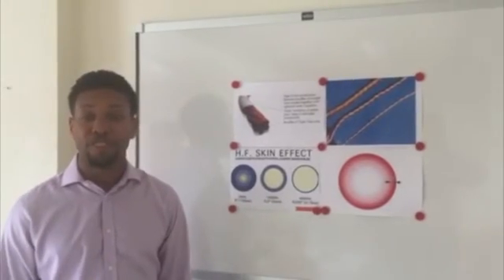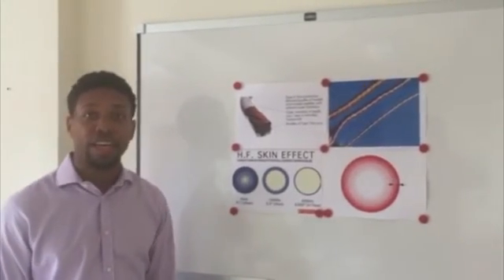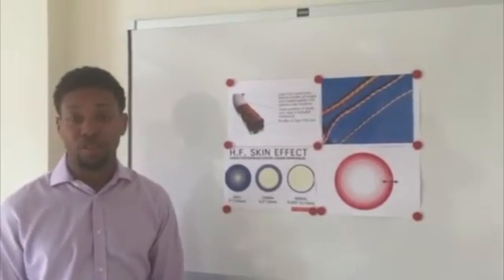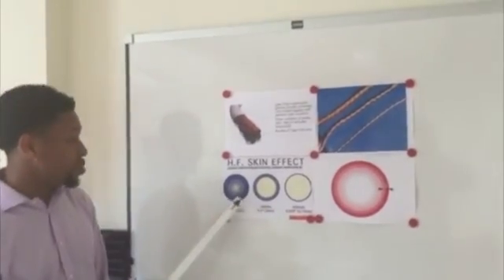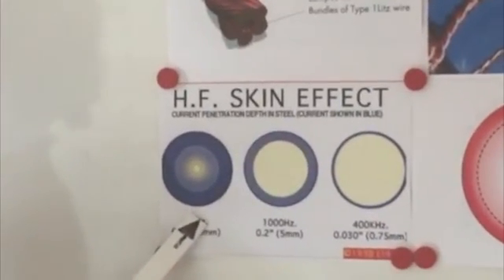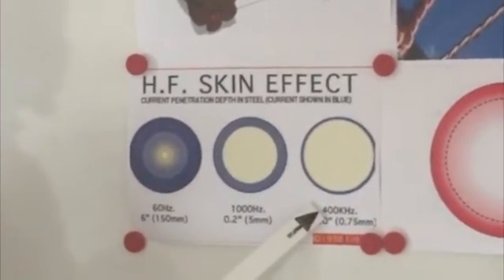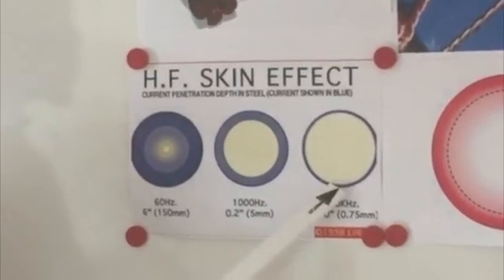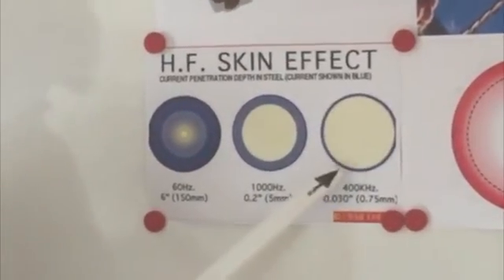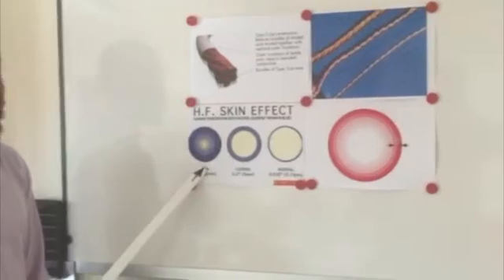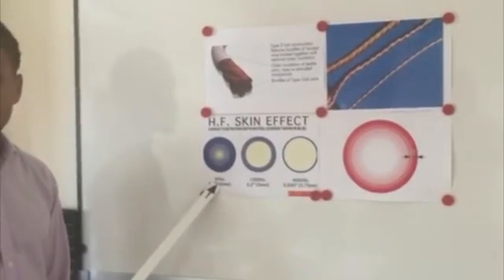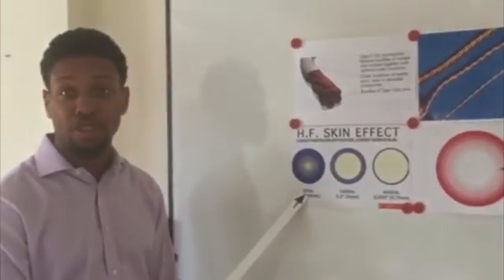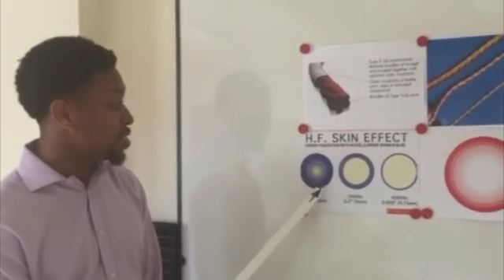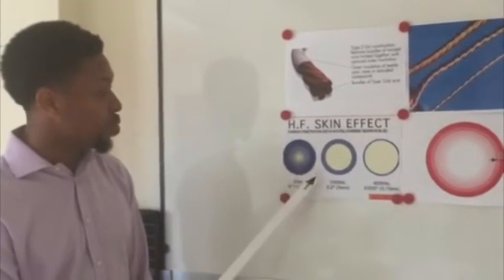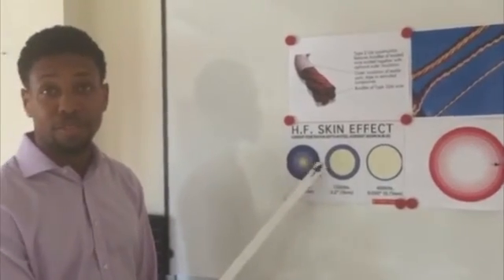A further method of reducing the skin effect is to change the frequency of the alternating current. As you can see from the diagram here, the blue represents the amount of current flowing within the cross-section. With the larger frequencies, there's a very small amount of current flowing, very small skin depth, compared with the smaller frequency, 60 Hz, which is a lot closer to what we actually use for our alternating current, has a much larger amount of current flowing and a much deeper skin depth.